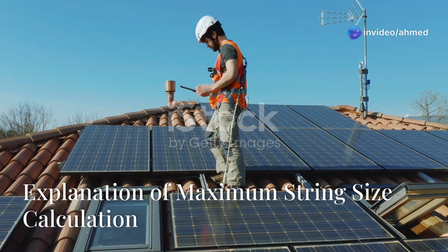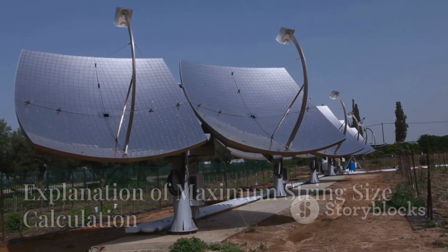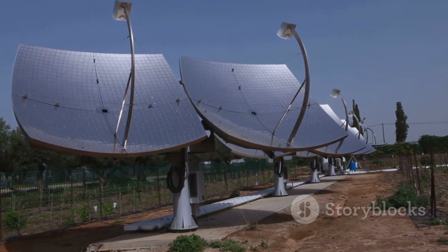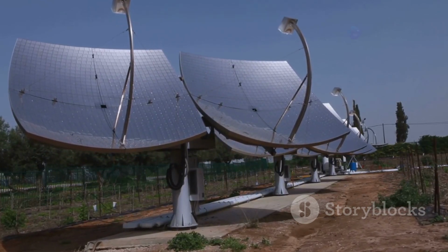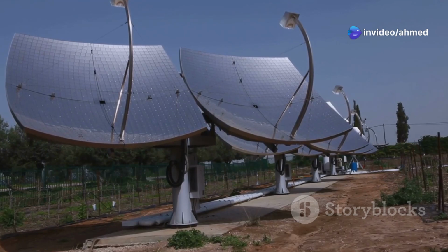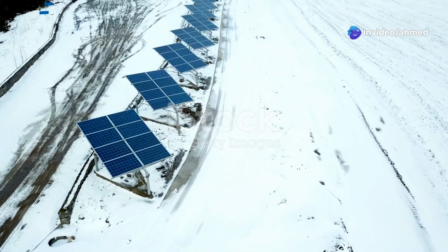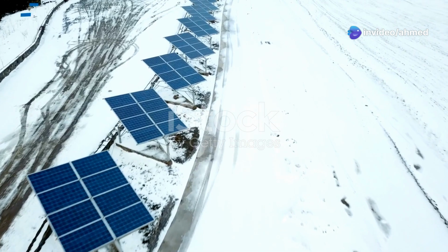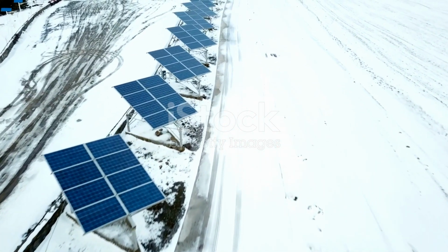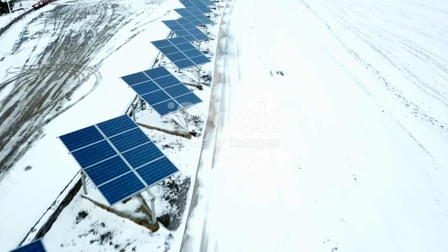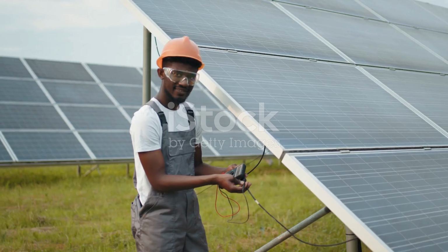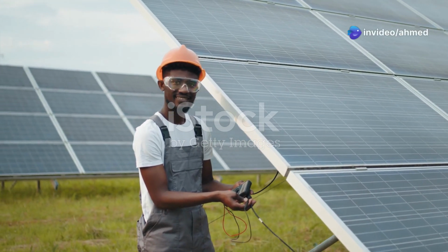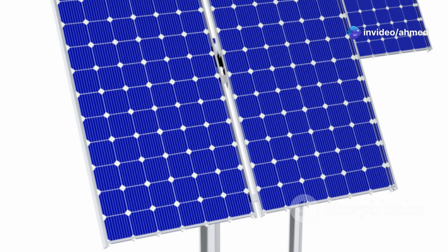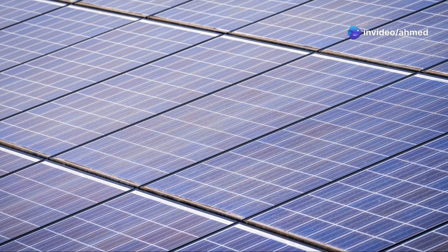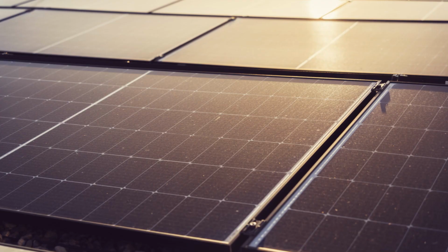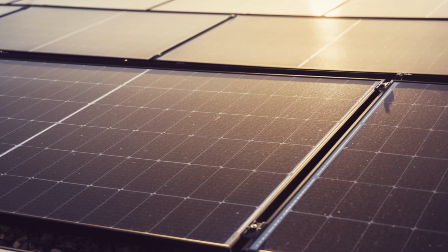How to calculate maximum string size? The maximum string size is the maximum number of PV modules that can be connected in series and maintain a voltage below the maximum allowed input voltage of the inverter. The module VOC_max is calculated using the coldest temperature, when the modules produce the highest expected voltage. This voltage is considered a safety concern and is addressed by the NEC. Unlike our adjustments to the calculation for string performance in hot conditions, there is no adjustment or adder for mounting type for this calculation in coldest conditions.